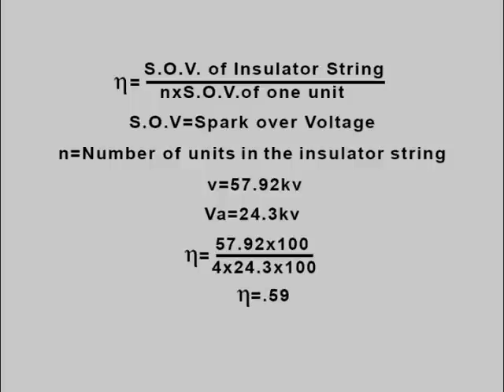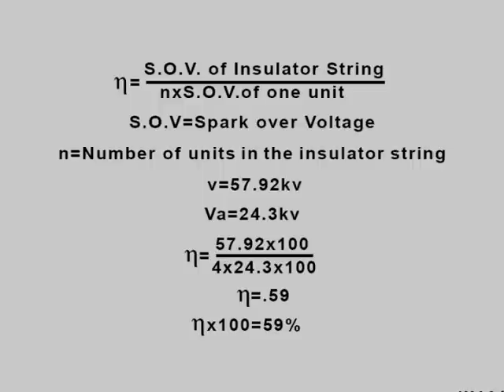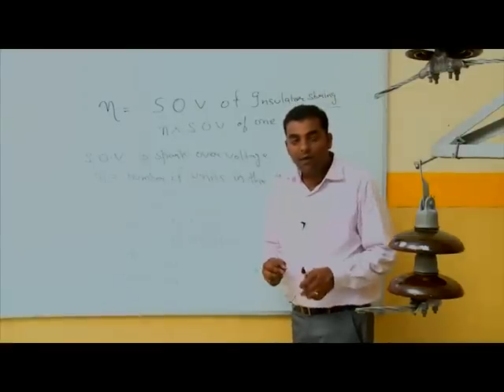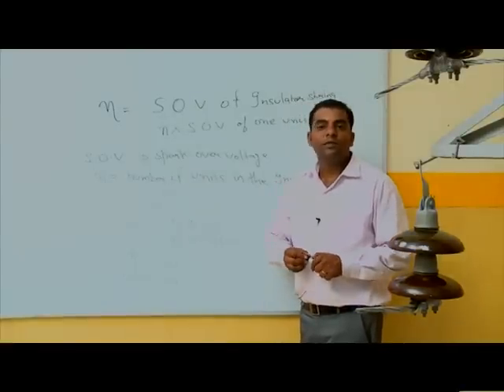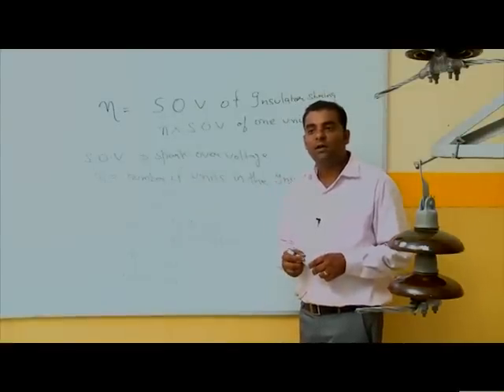After the calculation, the result is 0.59, and the percentage efficiency of the insulator string is eta into 100, which is equal to 59%. With this result, we can conclude that the efficiency of that particular insulator string is 59%. Now we will calculate the value of the transmitted voltage with the help of the capacitance divider.